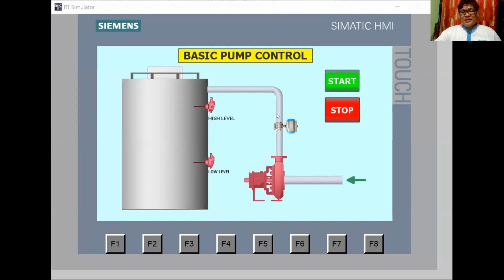To operate this kind of pumping, when I start pressing this push button, the valve first will open before the pump will start. If I press the stop push button, the pump will first stop before the valve closes. That is the logic.